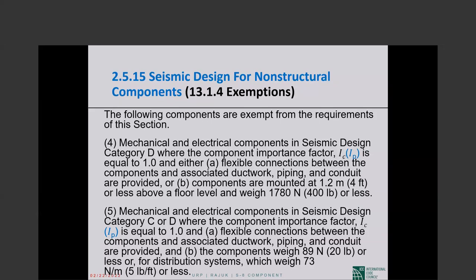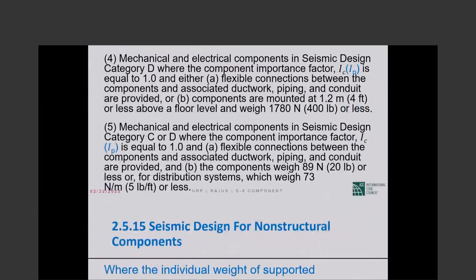Final one: mechanical and electrical components, design category C or D, where I sub P is 1, and flexible connections between the components and associated ductwork, piping, and conduit are provided — here it's and, not or — and the components weigh 20 pounds or less, or for distribution systems, 5 pounds per linear foot or less. Anyway, you have to read them closely, but I think they're totally understandable upon reading. The main thing is that there is a significant list of exemptions to start with.